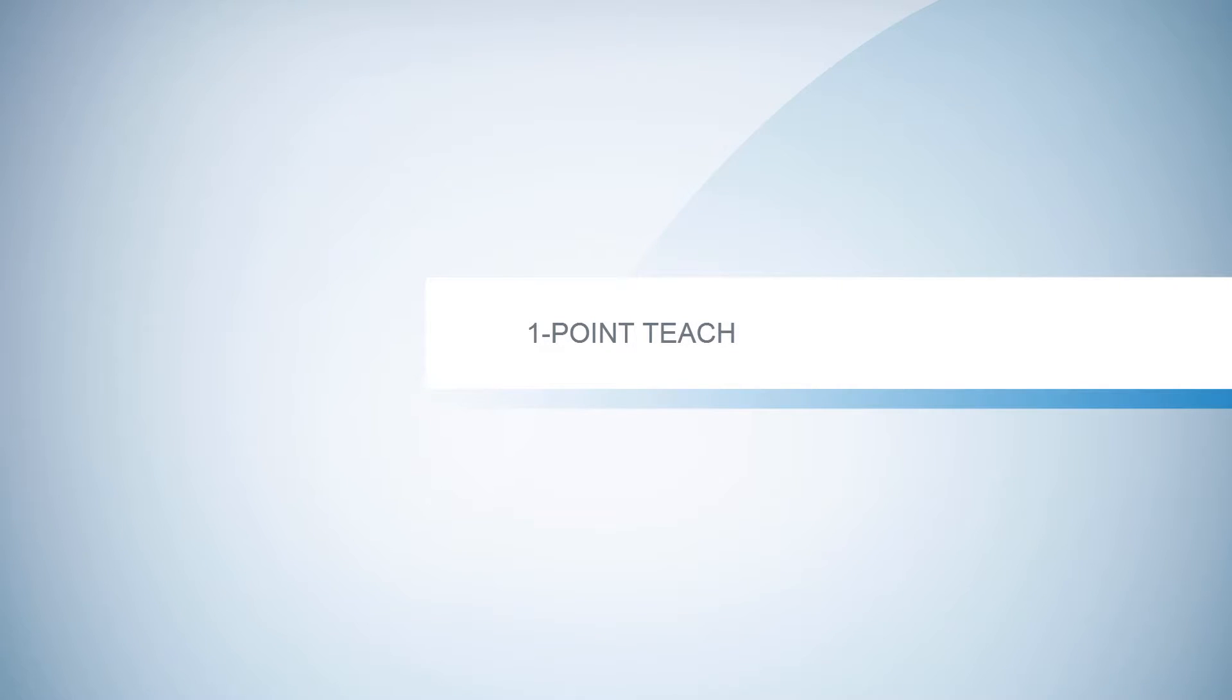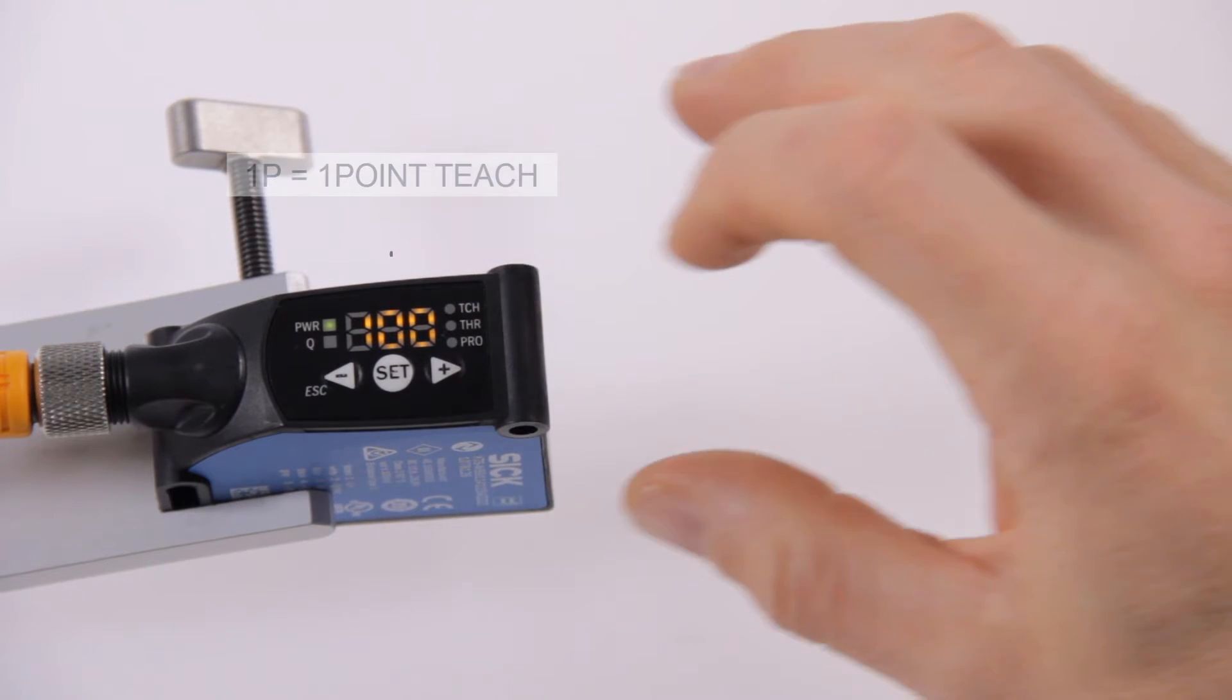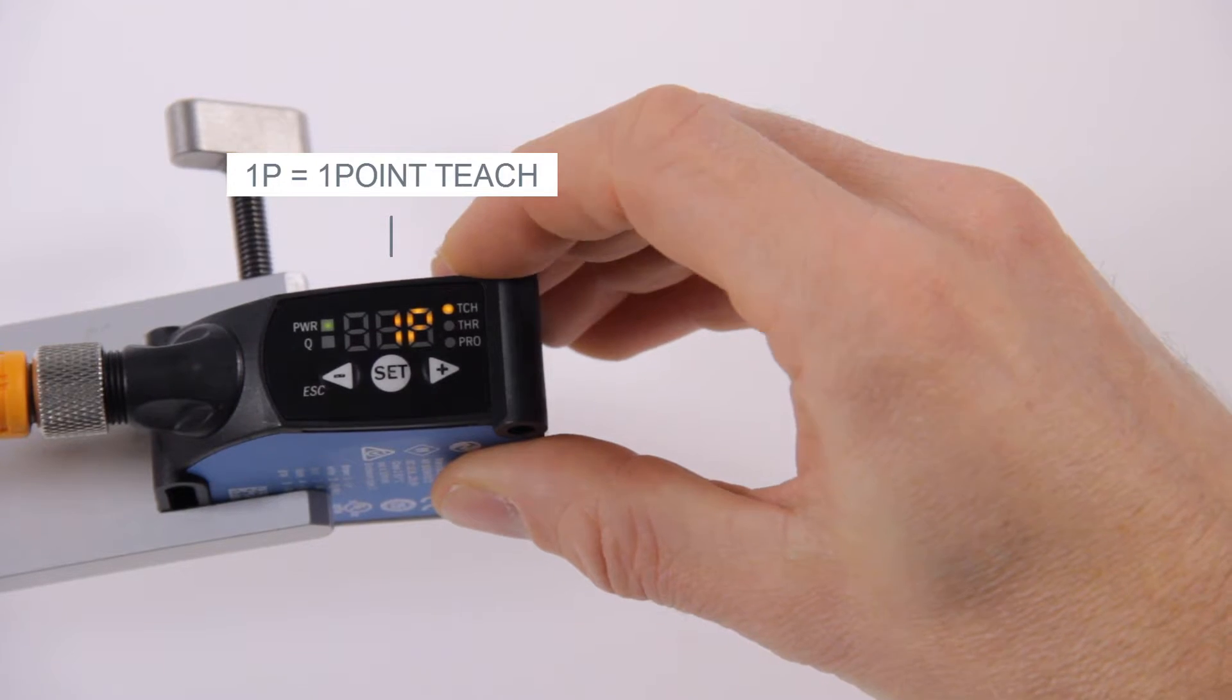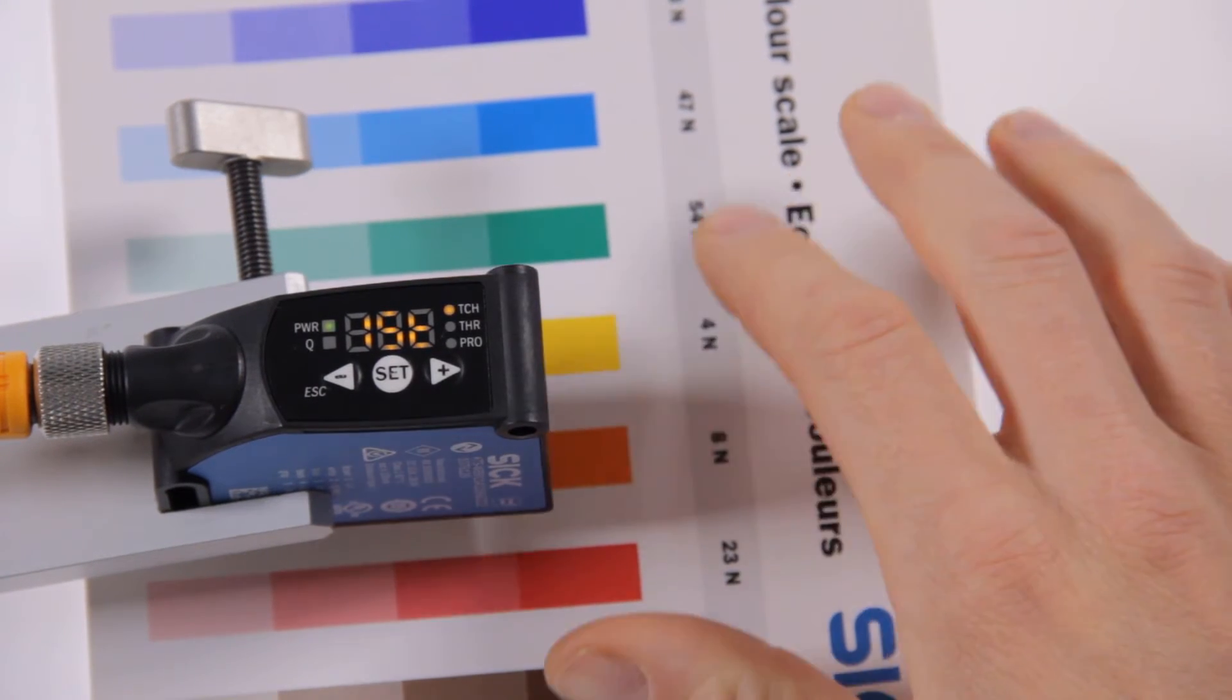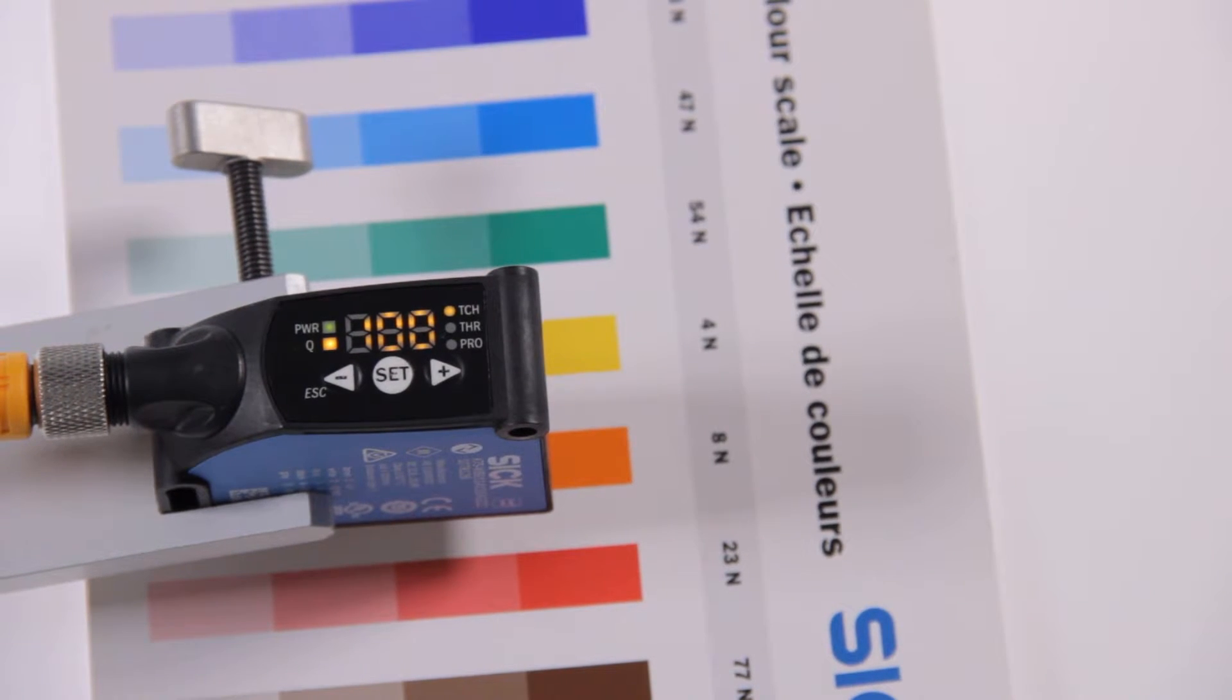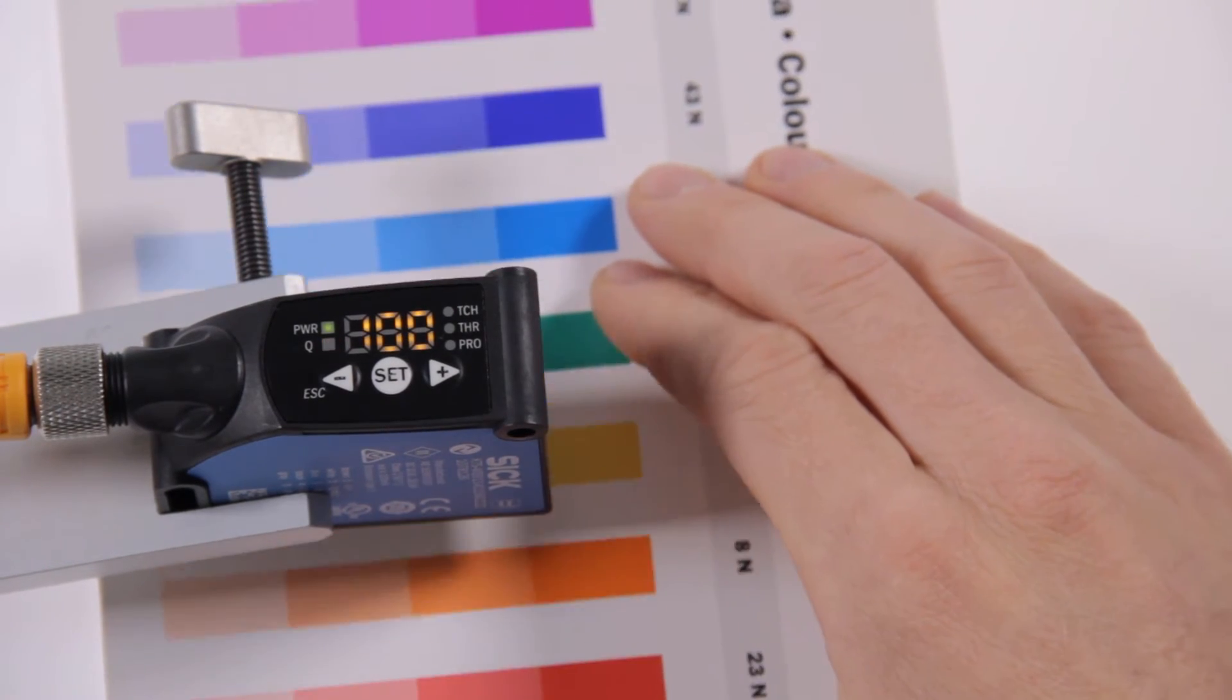One point teach. The one point teach is also called the color mode. In this mode, the sensor is working like a color sensor and is recognizing colors. Select the teach-in method 1P for one point teach and confirm with SET. Move the colored mark under the sensor and press SET. The digit value always shows 100 as the quality of teach. Now only the taught-in color is detected by the sensor.